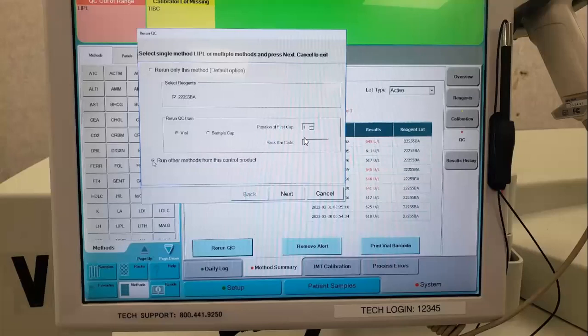If you do not click this, you will rerun the whole panel that is used on this QC, and you will get some that even if they pass the first time, if you rerun them, they might not pass. It doesn't happen very often, but we don't want to have to keep rerunning QC. And this is the only one that's out, so it's the only one we really need to run.